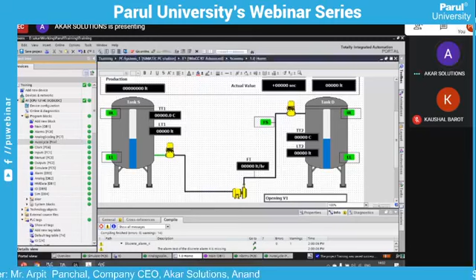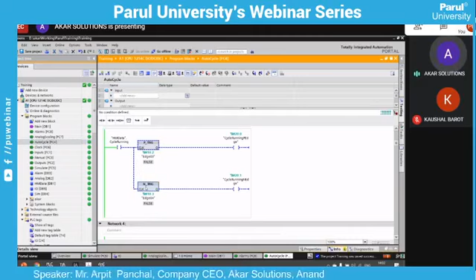So let's see how the cycle is written into the logic. First of all, we are checking all the interlocks. If there is any alarm that the destination tank is full, if the source tank is empty, if the pump trips, or the pump run feedback, then it will give you one signal that the plant is ready to run. Then when we start the signal and the sequence is not completed or not aborted, the cycle can start. We are taking a positive trigger and a negative trigger. Positive and negative triggers are used to identify the starting and stopping of any particular state.